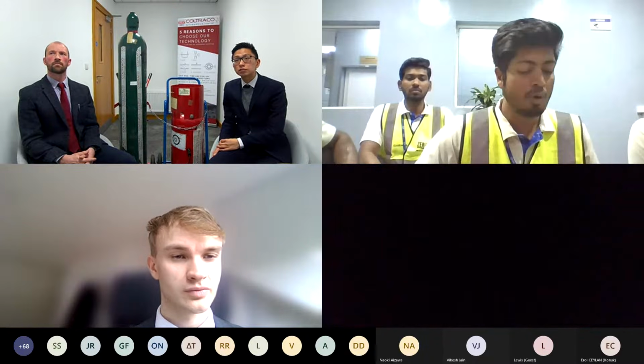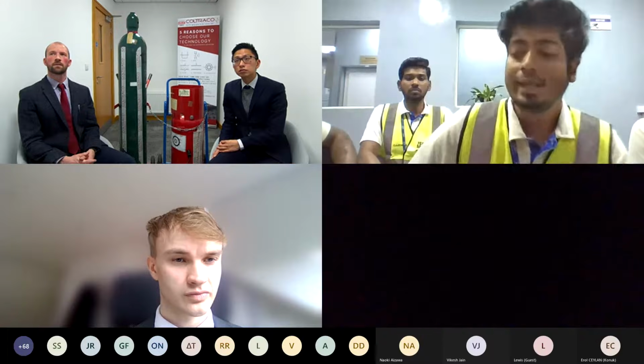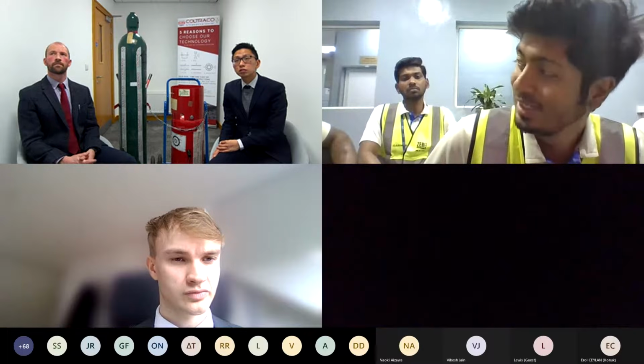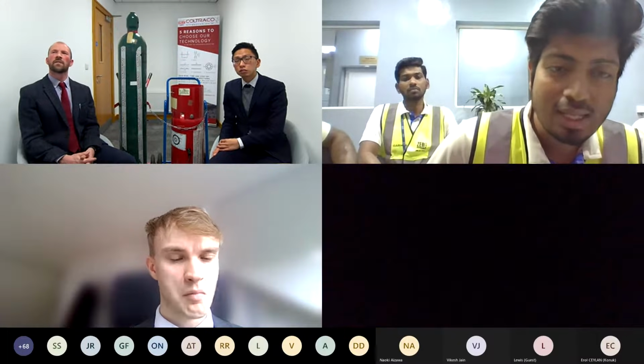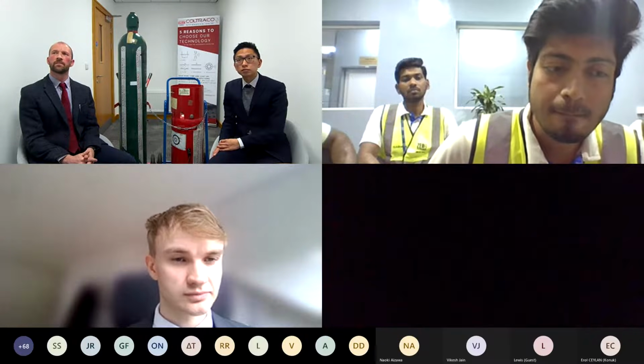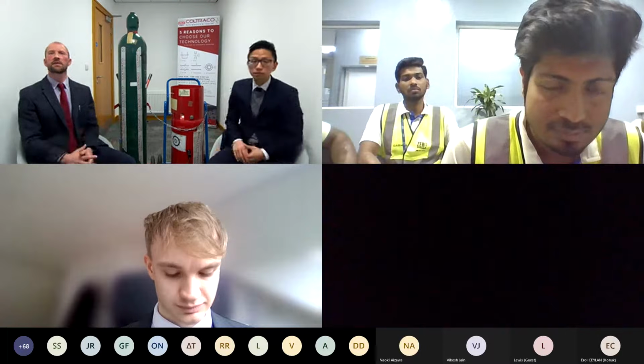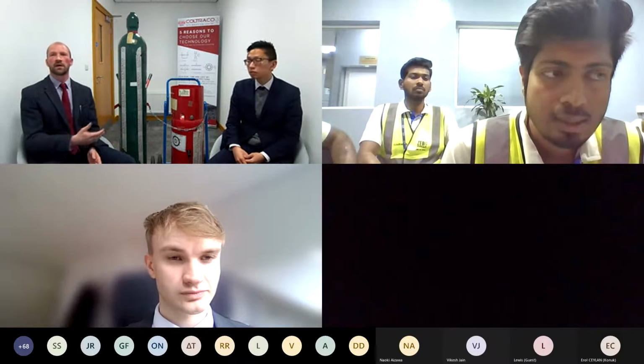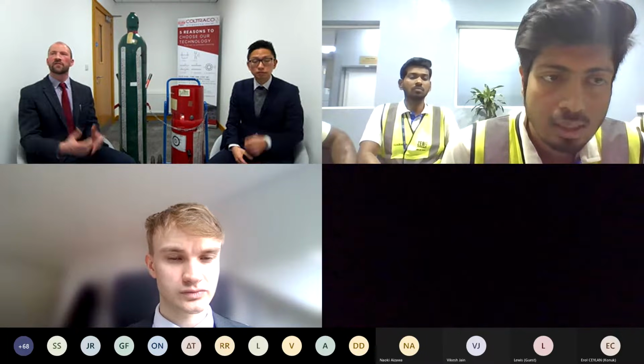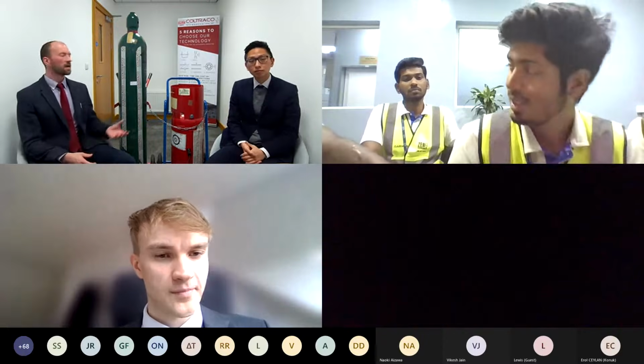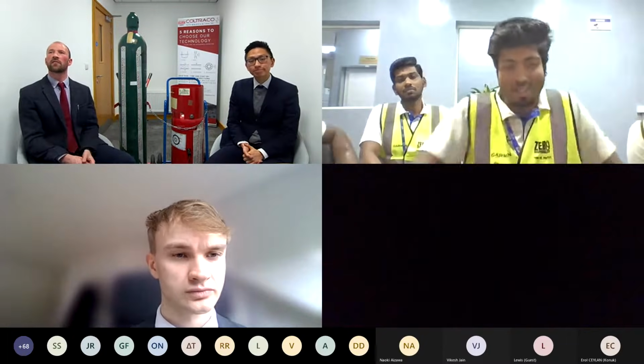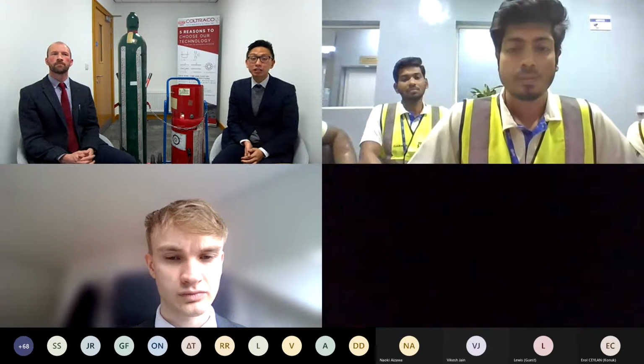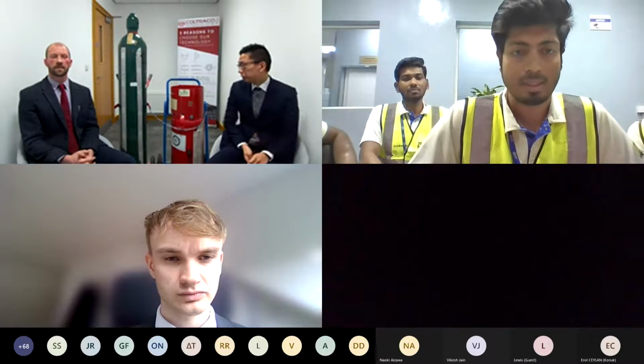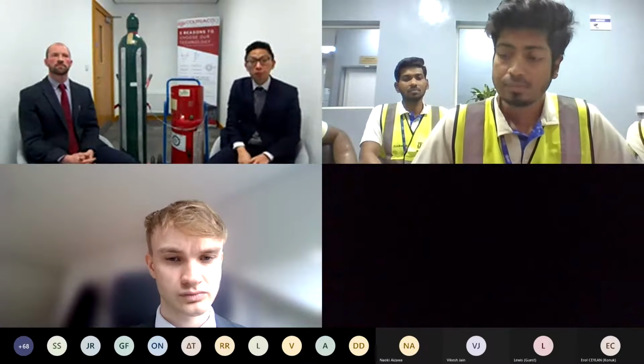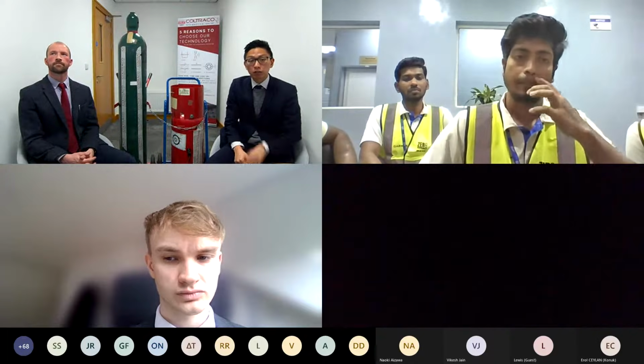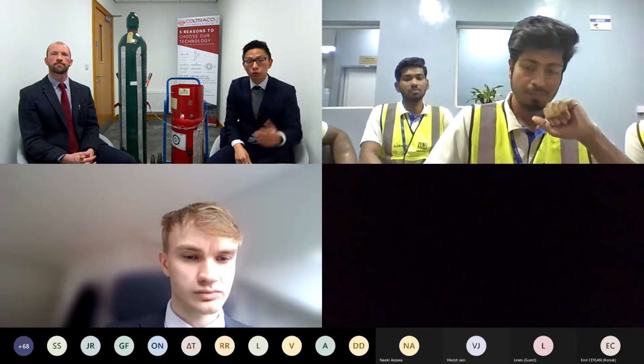First thing, can I measure the content of LPG mass? I think you were going to use it on LPG. Am I correct? Did you ask if you can use this on LPG? Yes, this is similar to what Adrian described before with monitoring other liquids, other than what you've seen here. Again, whichever agent you're looking at, if it is in liquid form, you can follow the same procedure and find the liquid level. It's more dependent on the cylinder size and the shape and things like that. So LPG, if it's stored in similar cylinders like this, that should be able to be tested with no problem. So get in touch with us if you have a different size and you have any concerns, and we will help you address it.